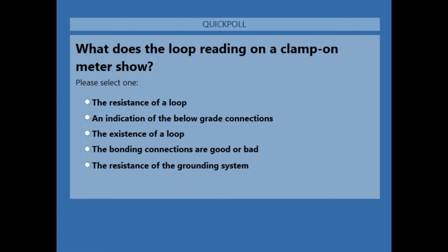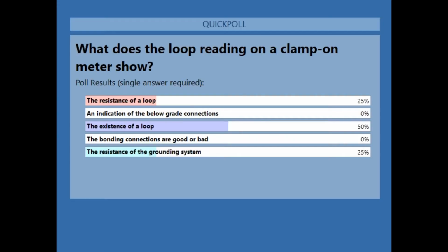So let's see what our audience thinks. Polling question coming up to a consensus. We've got a little bit of a mix in what the audience considers the value. What does it show? Well, it shows you most of the first four things, but it actually does not show you the resistance of the grounding system. It's only measuring that one pigtail that you've clamped onto. So what's really interesting about this answer is that we wish we could see the resistance of the entire system, but that's not what a clamp-on meter will show you.